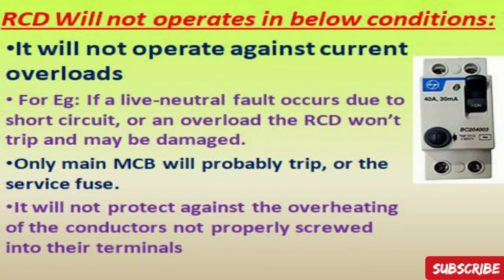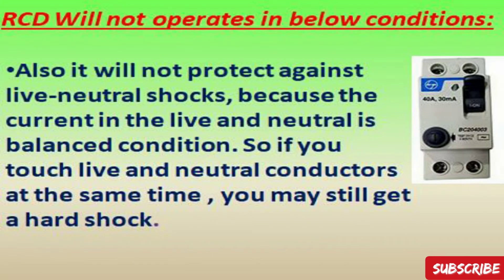RCDs do not operate in some conditions. First, RCD will not operate against current overloads. For example, if a phase-to-neutral fault occurs due to a short circuit or overload, the RCD won't trip and may be damaged — only the main MCB will probably trip or the service fuse will fail. Additionally, RCD will not protect against overheating. For example, if conductors are not properly screwed into terminals, heat will be generated automatically, and the RCD will not protect in that condition.